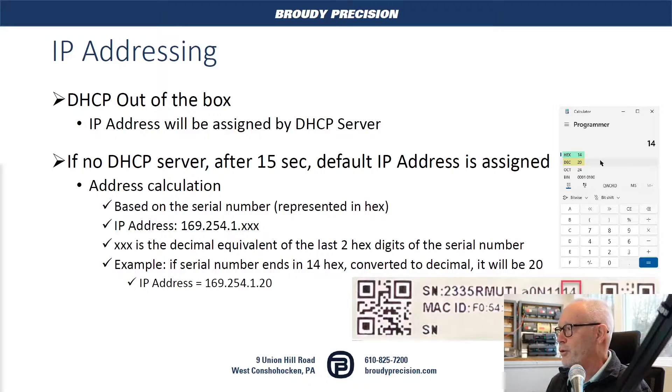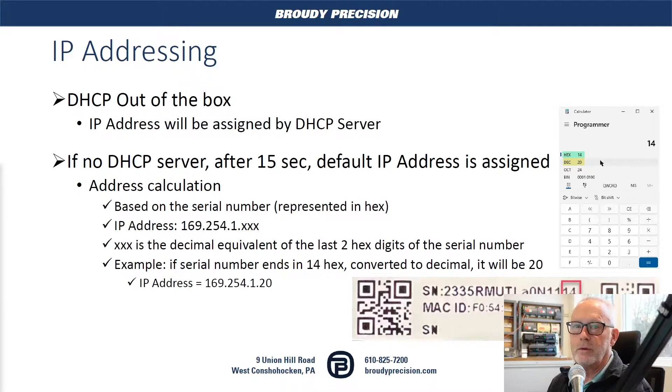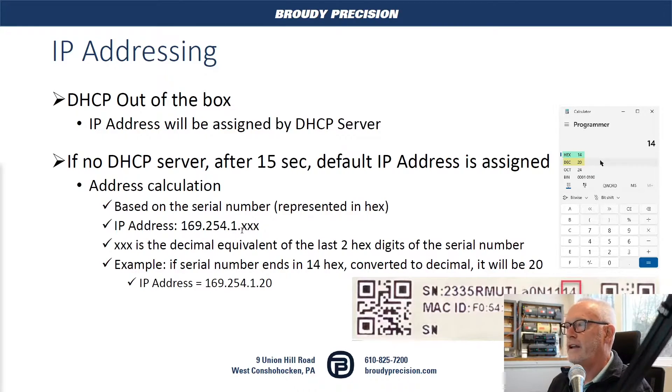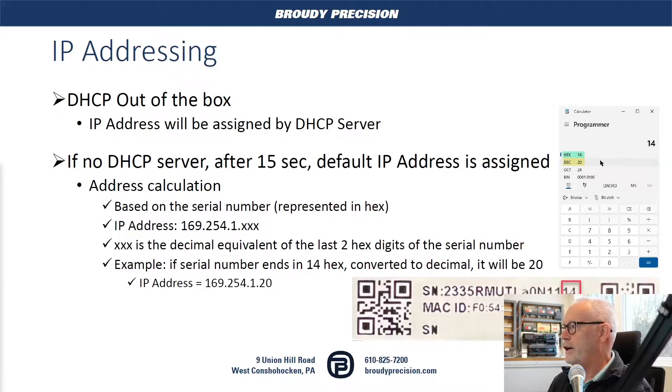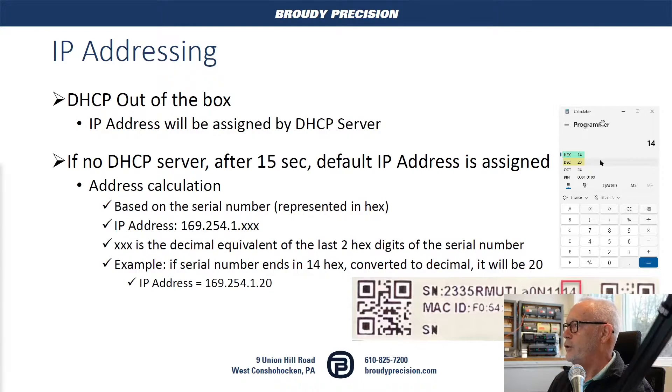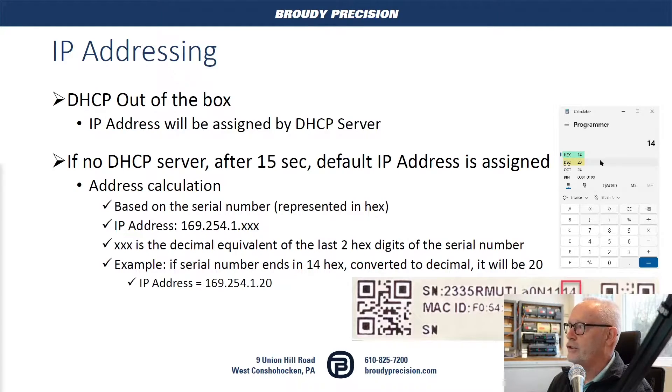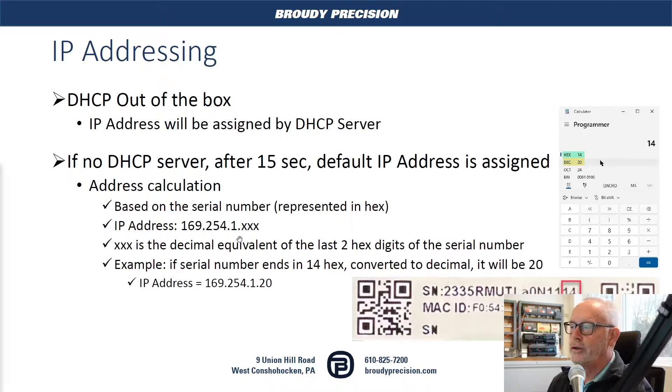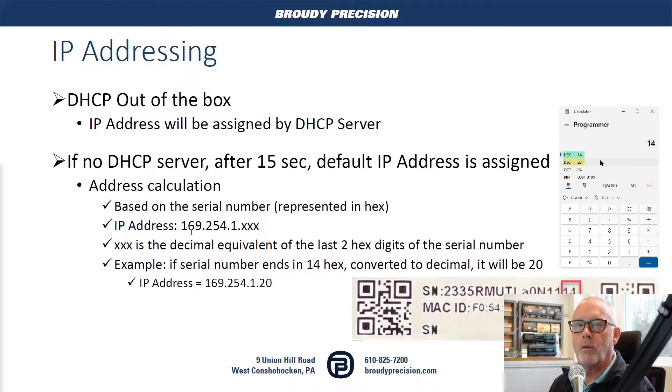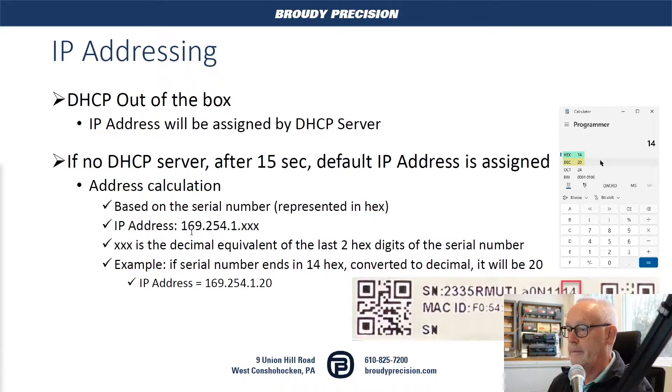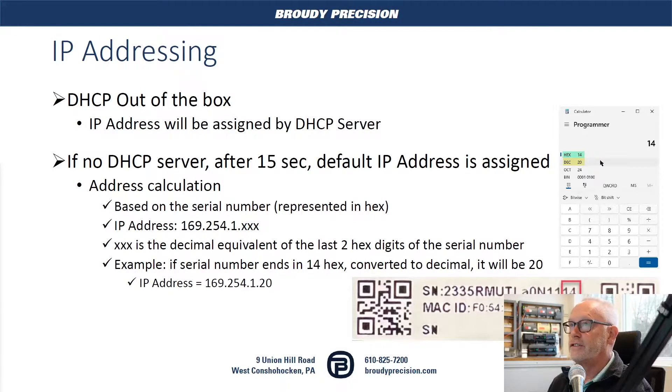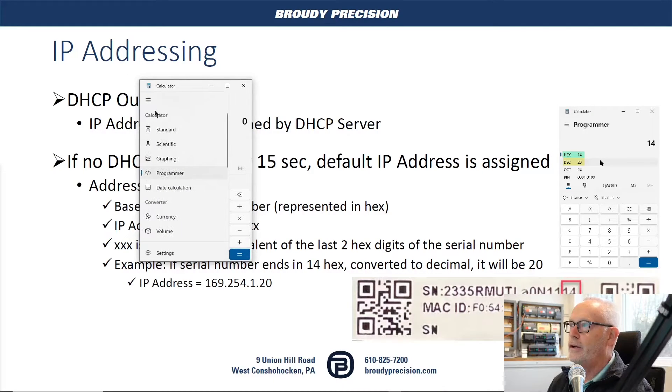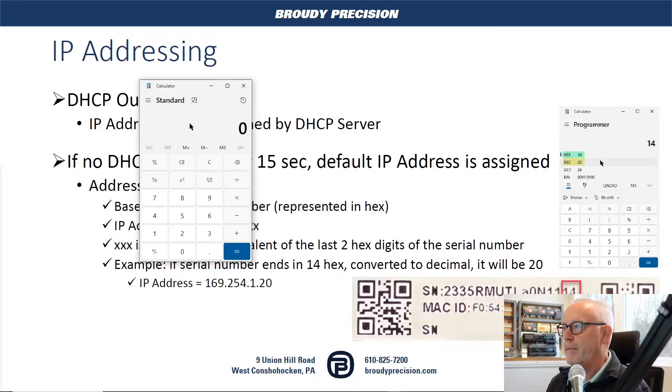So the number 14, the last two digits, you want to convert them to decimal, and that will be what you use for that fourth octet in the IP address. So in the example here, it's 14. And if you use your Windows calculator, set it for programmer mode, you enter 14 hex, it will show you the decimal value is 20. So when you do your address, that controller will come up as 169.254.1.20. And so the real thing there is just making sure you look at your serial number, get those last two numbers. Typically, you're going to have your calculator.